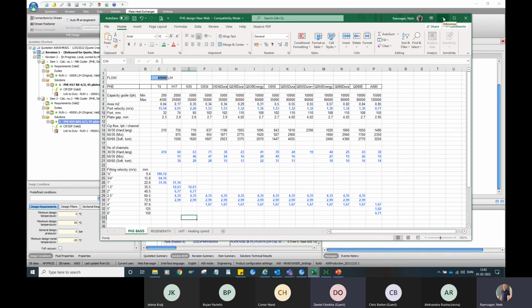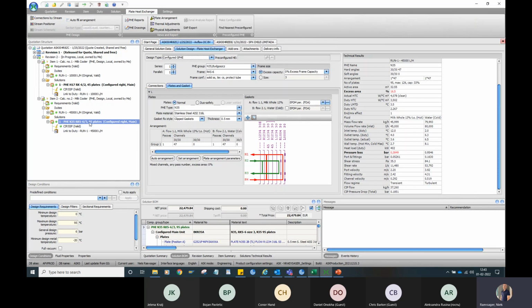See, what I came up with here is an N35 with 95 plates. And if you look here, to do this job with my design on an N35, I need 32 square meters. One quick way of checking whether it could be possible in a H17 is simply take the area of 32.5 and divide that by 0.17, which is the area per plate for a H17. That will give you an indication that you need a H17 with 191 plates in it.